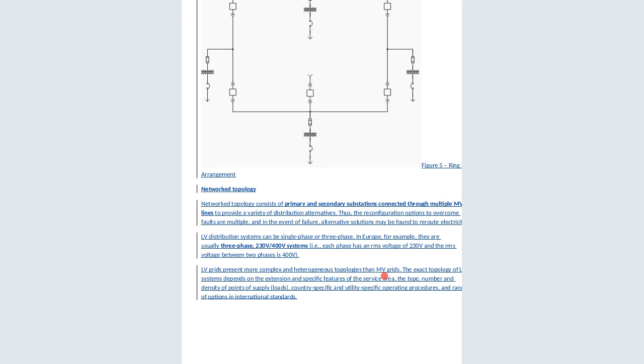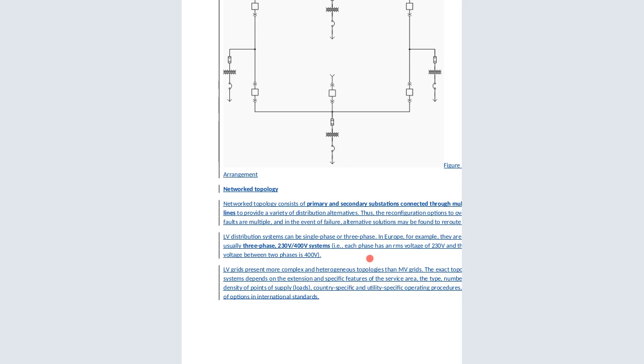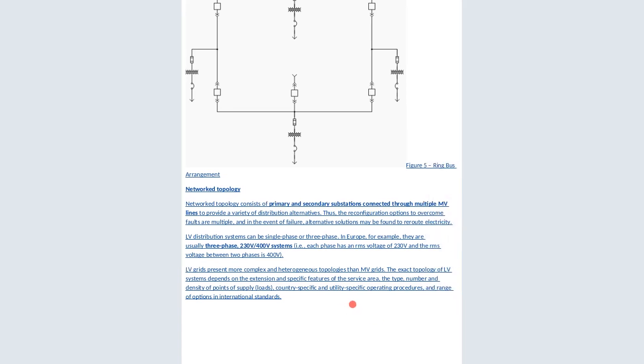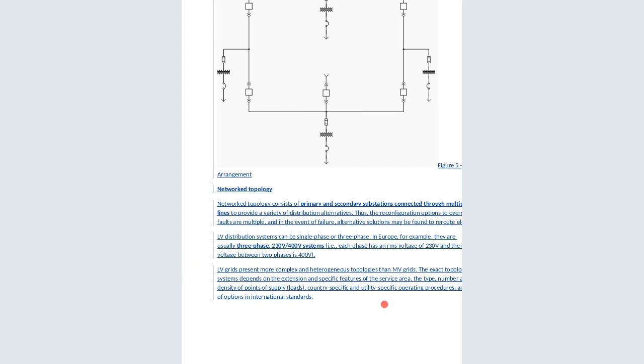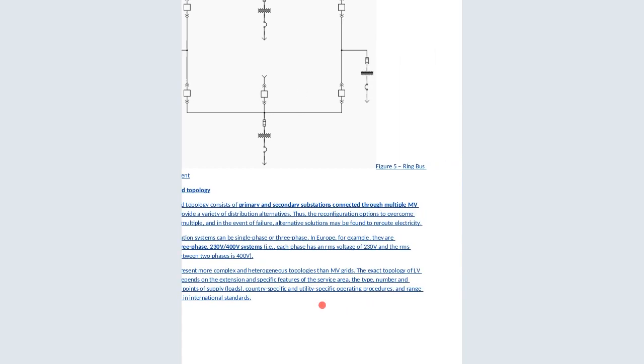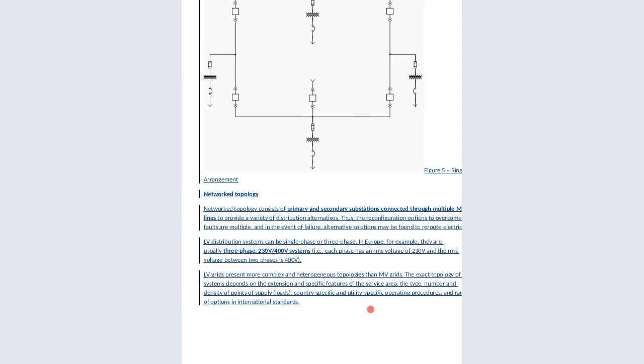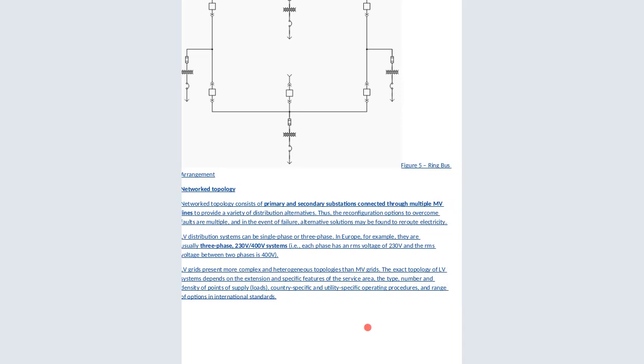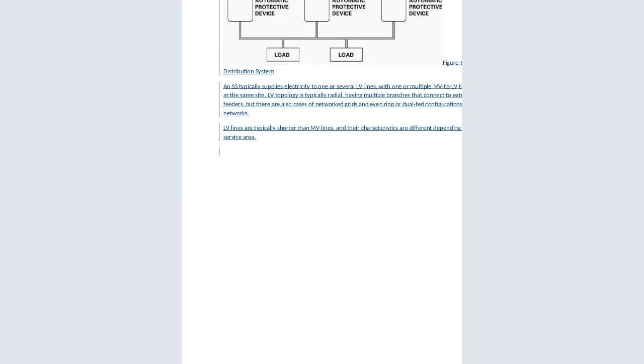So you can now see the LV distribution system can be single phase or three phase. For example, they are usually three phase, 230V/400V systems. Now the LV grid represents more complex and heterogeneous topologies than MV grids. The exact topology of the LV systems depends on the extension and specific features of the service area, the type, number, and density of the point supply loads, country-specific and utility-specific operating procedures, and the range of the options and the standards.